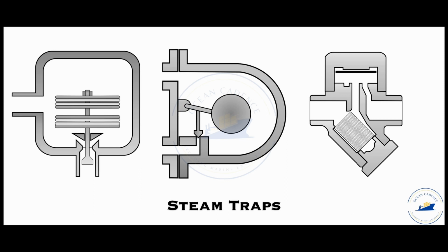But why so? We all know that the purpose of a steam trap is only to allow condensate to escape out from the discharge side of its line, so that whenever the steam is in its absolute condition, that is still in steam form, may it be saturated or superheated, the steam will not be allowed to pass through the discharge line. The idea behind this is to make sure that whenever the steam converts into water, it is appropriately drained and returned into the return circuit, and thereby causing negligible loss of live or utilizable steam from the circuit.